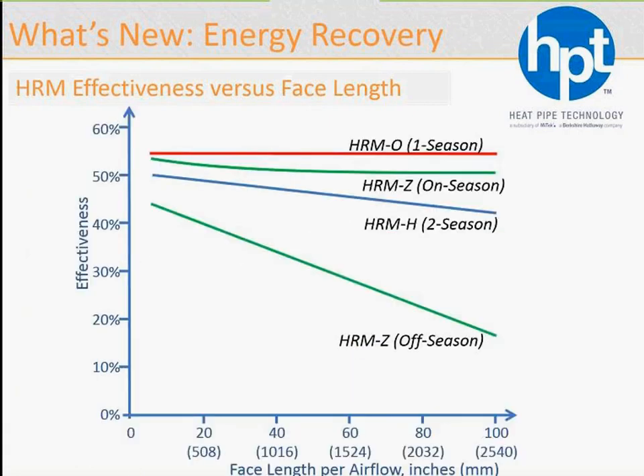Okay, how do those configurations compare? On the left is the effectiveness chart, which, some of you may not be familiar, shows what a device does relative to the theoretical maximum recovery, as it applies to sensible and as it applies to latent. On the lower line, in metric and in inches, is the individual length of each airstream. So HRMO takes the cake on this particular one, at about 55% recovery.